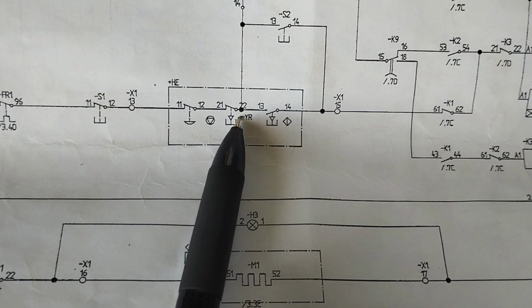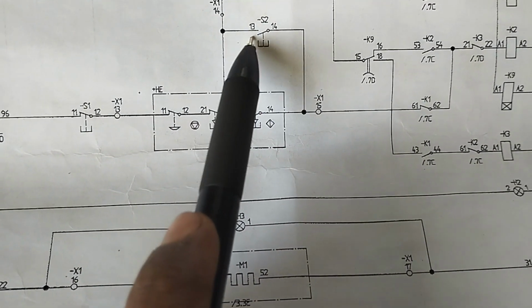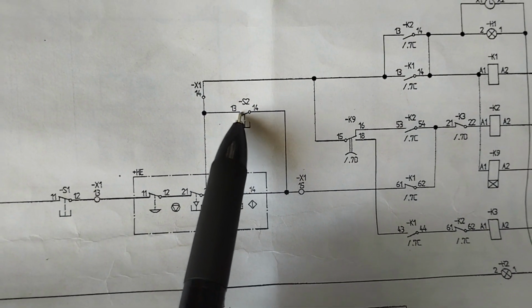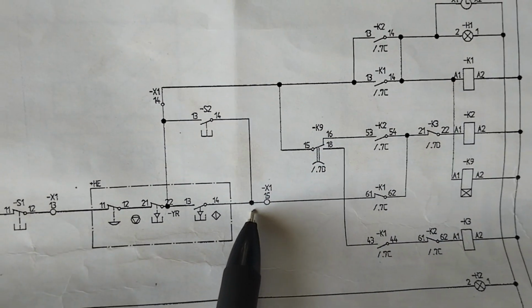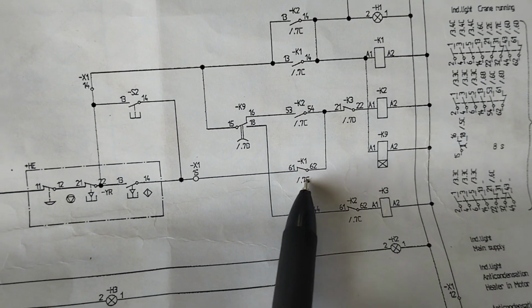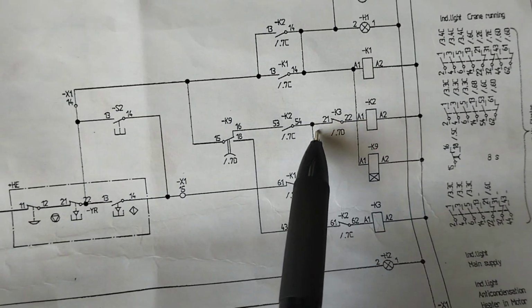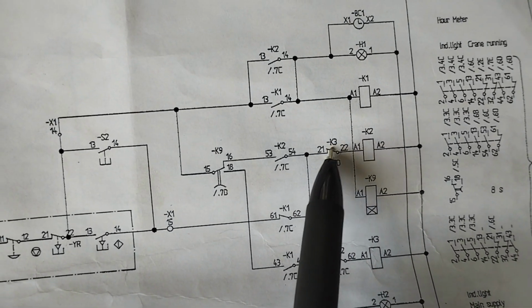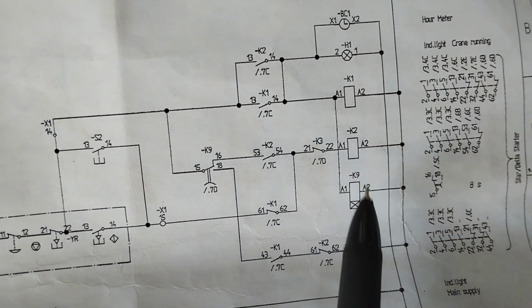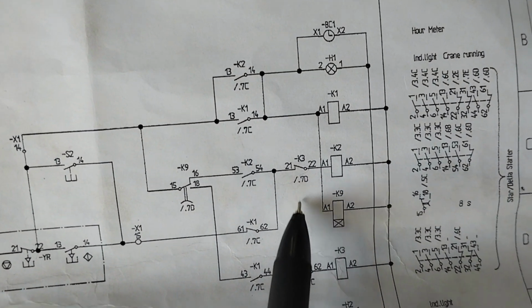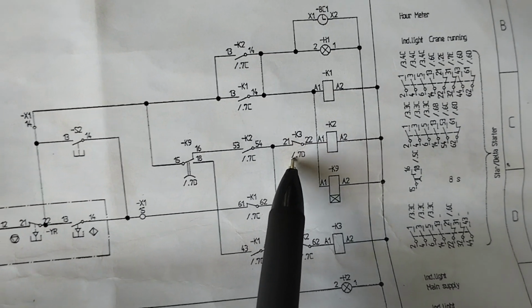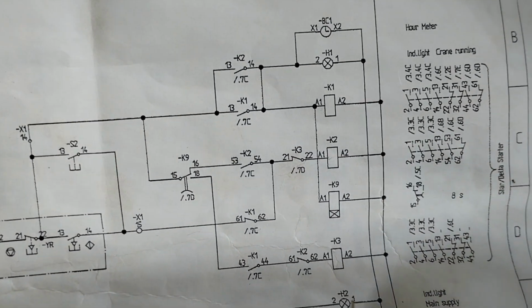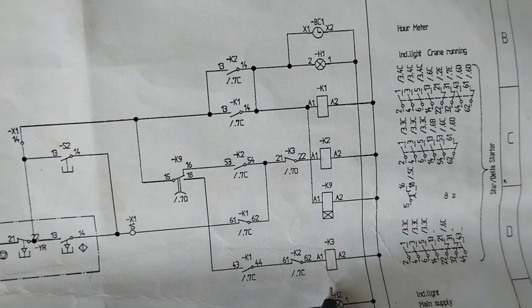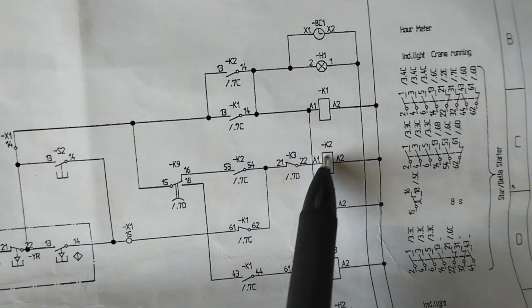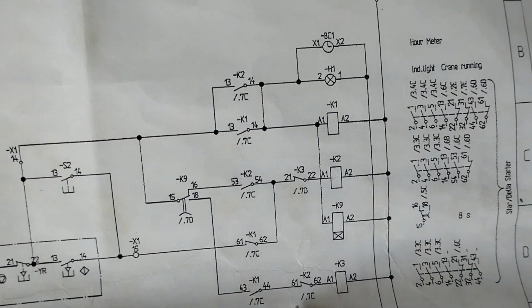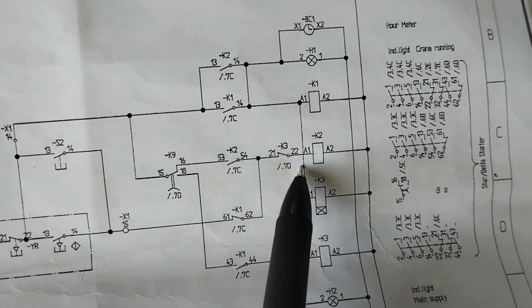Okay, so after that power will come here. And what is this? S2 is the start push button. If you press it, it will make the contact and power will transfer. This is a normally closed contact. Power will come to here. This K3 is very important, 21 and 22. K3 is the delta contactor, and this is the normally closed contact of K3. So if K2 energizes, K3 will not energize, and if K3 energizes, K2 will not energize. So this is the interlock. You can see K2 and K3 interlock. So this is normally closed.